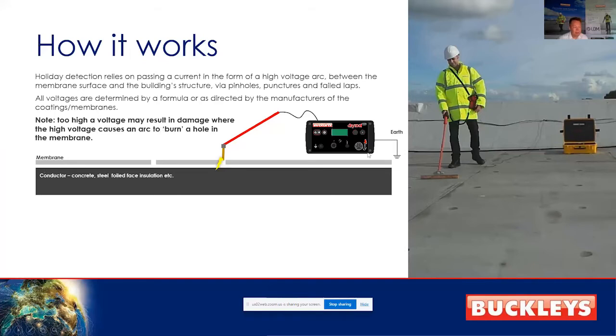As you can see in the picture, all we're going to do is earth our machine to something that is conductive. In this scenario, we have a lightning conductor up on the roof, and we've taken an earth cable to our machine. All we're going to do is set a defined voltage on the machine dependent on the thickness of the material, and we're going to start brushing over the top of the insulator.